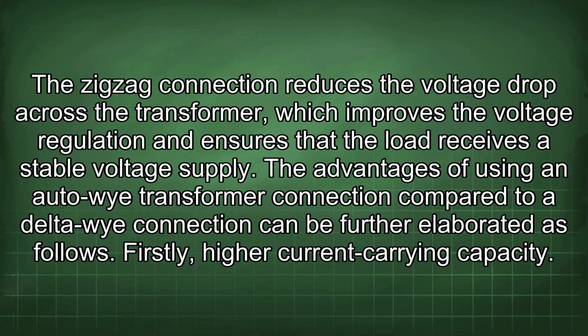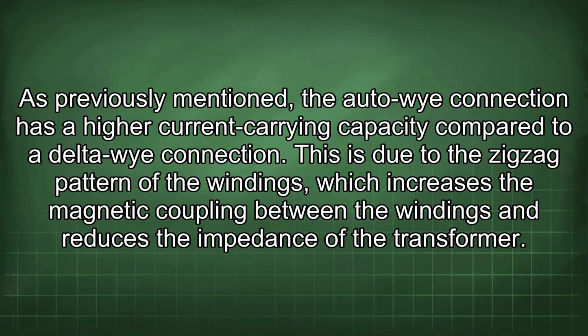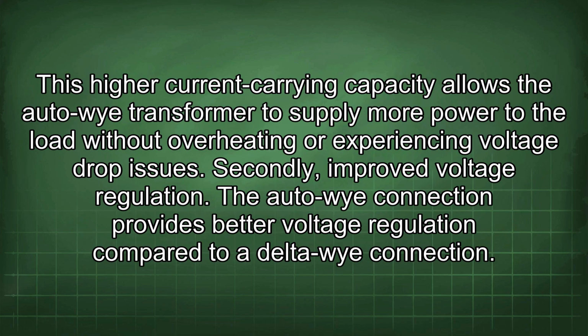The advantages of using an Auto-Wye transformer connection compared to a Delta-Wye connection can be further elaborated as follows. Firstly, higher current carrying capacity. As previously mentioned, the Auto-Wye connection has a higher current carrying capacity compared to a Delta-Wye connection. This is due to the zigzag pattern of the windings, which increases the magnetic coupling between the windings and reduces the impedance of the transformer. This higher current carrying capacity allows the Auto-Wye transformer to supply more power to the load without overheating or experiencing voltage drop issues.